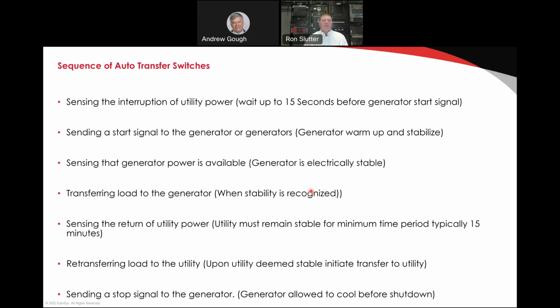So the ATS senses the return of utility power. It can sense the return, and it can be stable or it can be unstable. What does that mean? You can have situations where the power returns for the very first time, but we have tree limbs all over the utility lines, and the power is fluctuating. The phases are going off and on because they're trying to clean up these issues on the power lines. So it may be stable or it may be unstable. There's a period of time, usually 15 to 30 minutes, that we expect the utility has to be stable. And once it's stable for that period of time, the ATS can say, okay, now we're ready to retransfer the load.